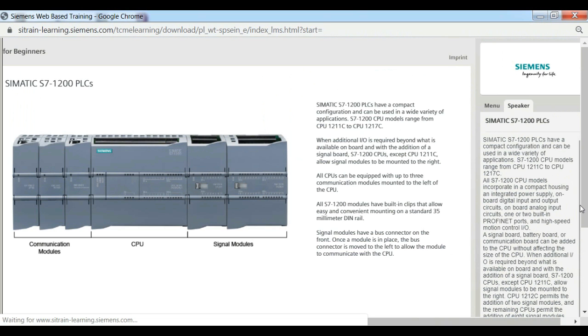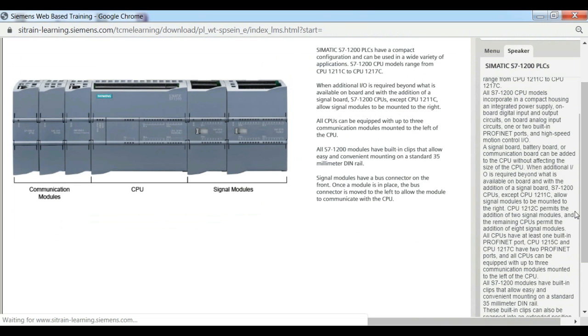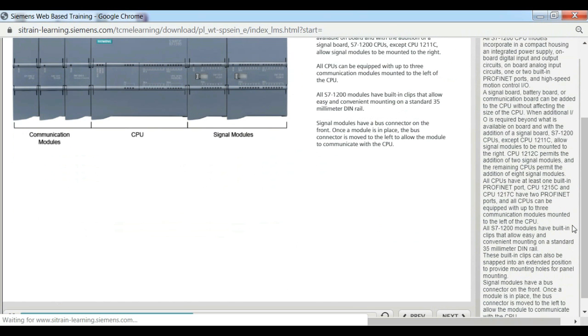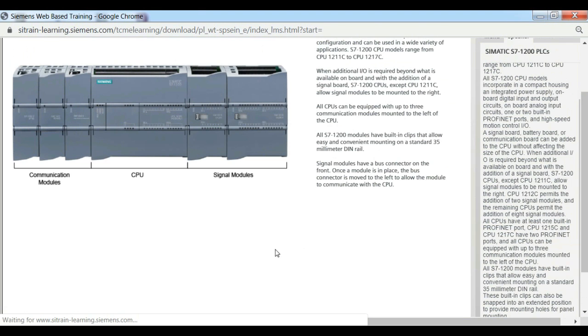S7-1200 CPUs except CPU 1211-C allow signal modules to be mounted to the right. CPU 1212-C permits the addition of two signal modules, and the remaining CPUs permit the addition of eight signal modules.